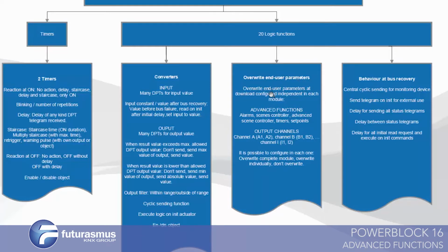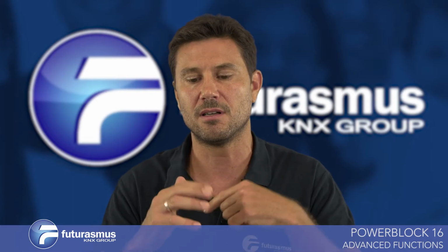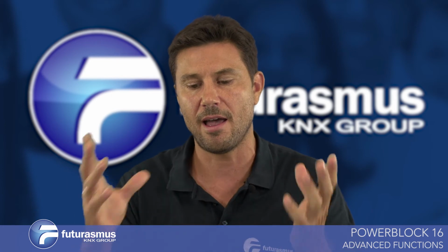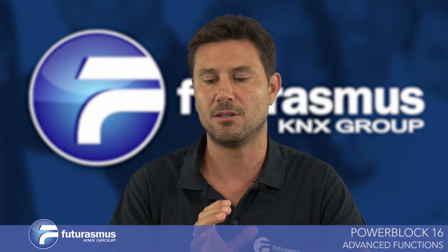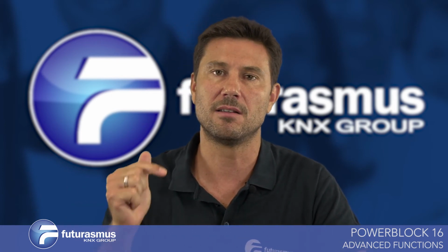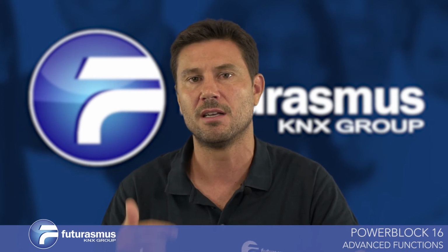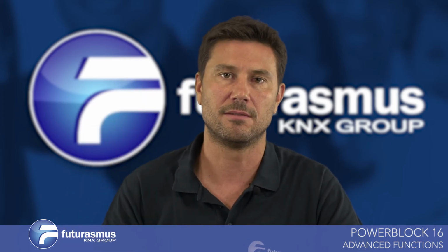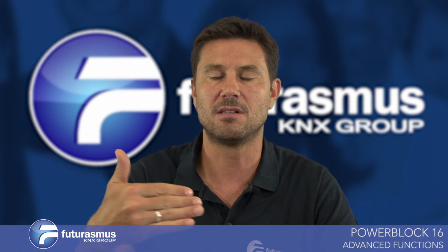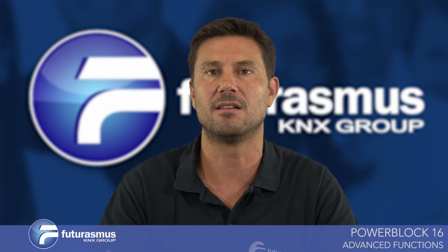And it's very nice. You can set any of the end user parameters individually how you want them. Then also the behavior at bus recovery, which is very, very important, so that you can set different behaviors for the device in general, to send the status values of the device after a delay, for instance, set different delay times and cyclic sending telegrams.